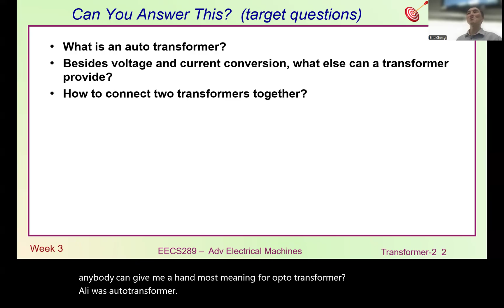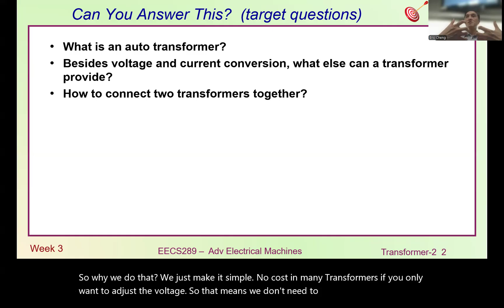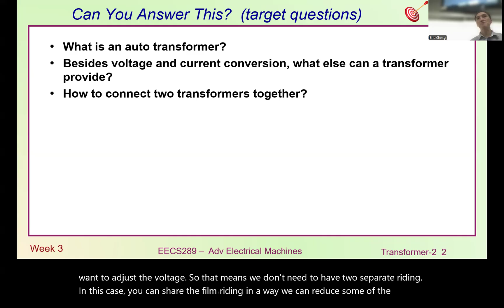So why do we do that? We just make this simple, low cost. In many transformers, if you only want to adjust the voltage, that means we don't need two separate windings. In this case, we can share the same winding. In a way we can reduce some of the cost, some of the wire. At least we can reduce the copper wire. So that's something we need to do.